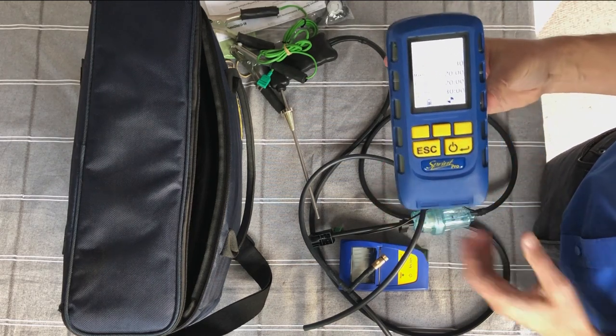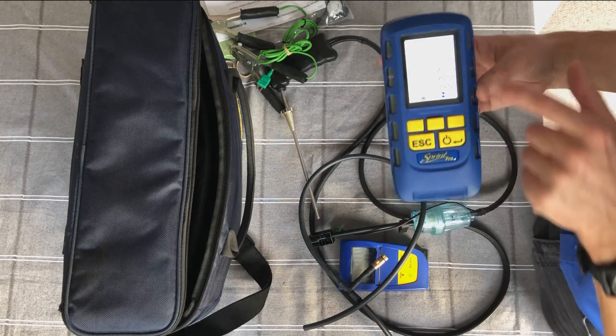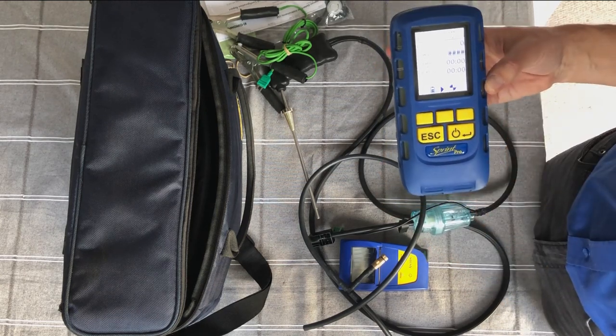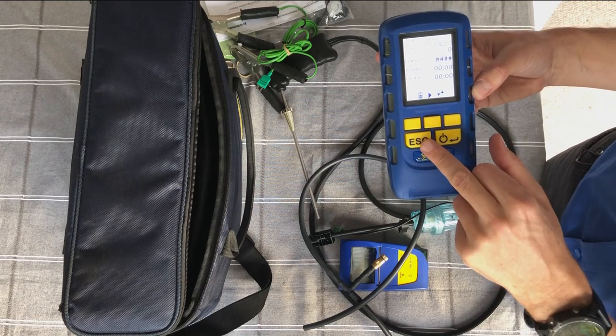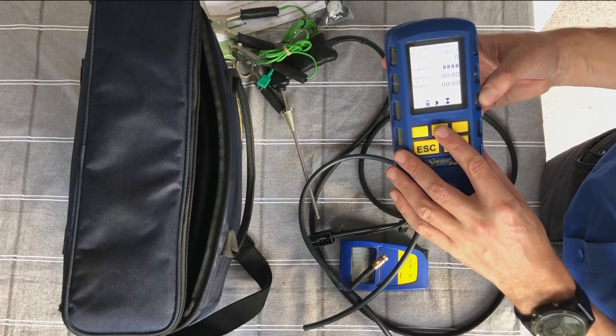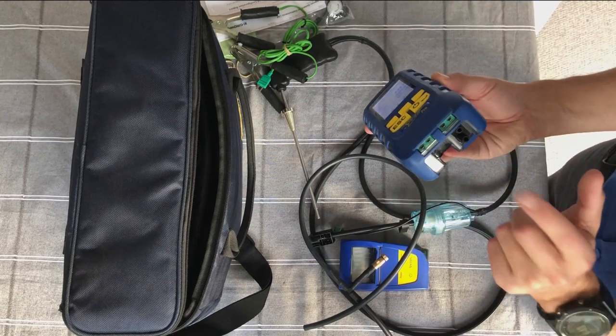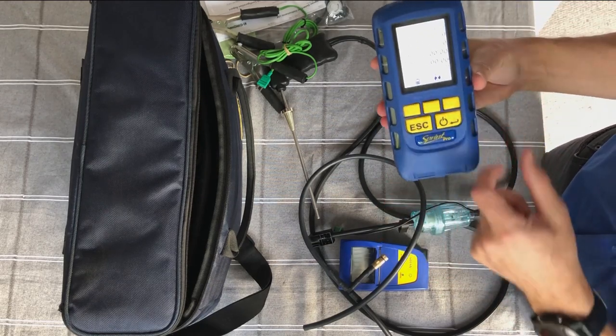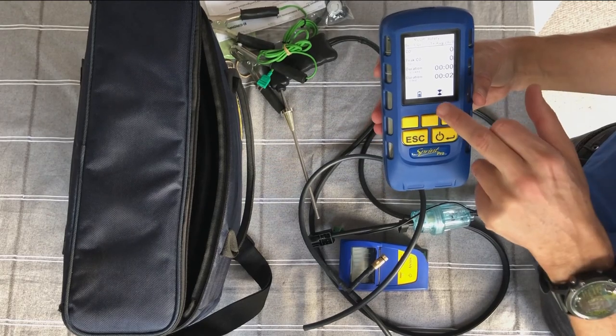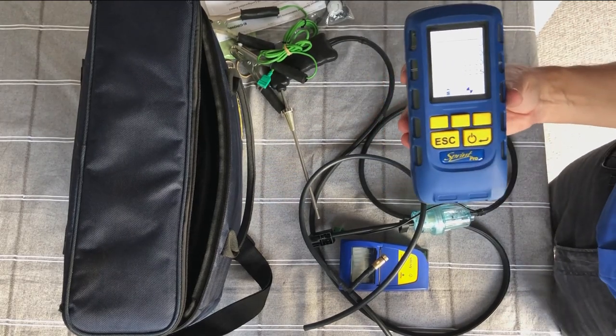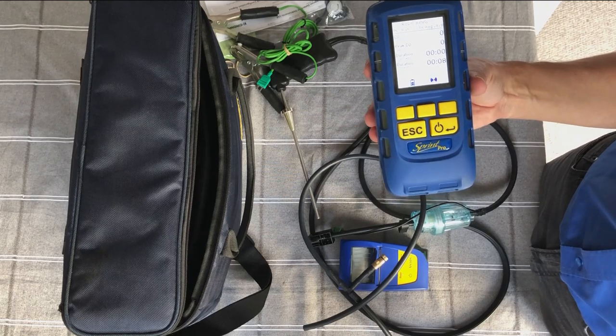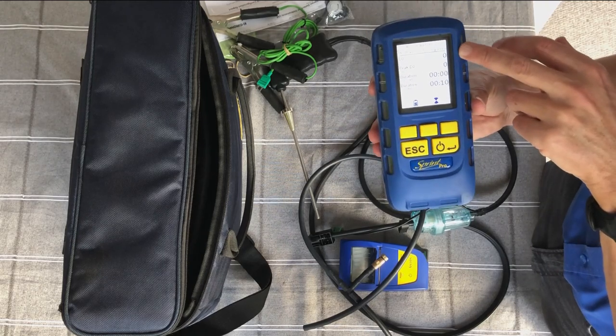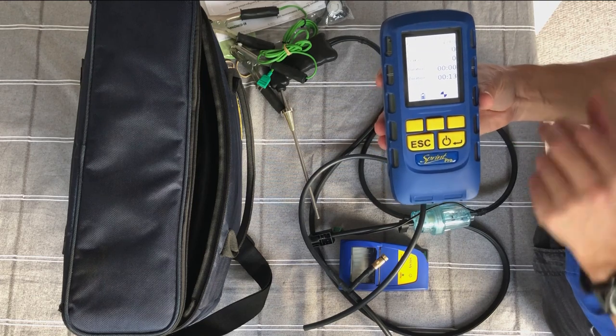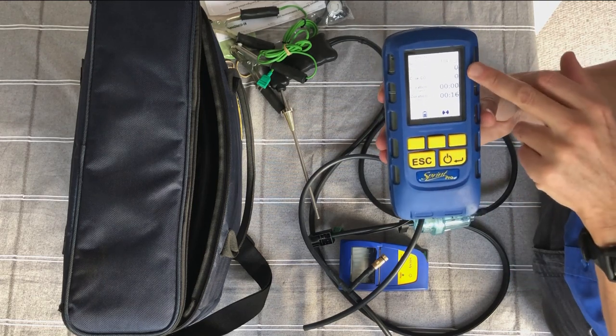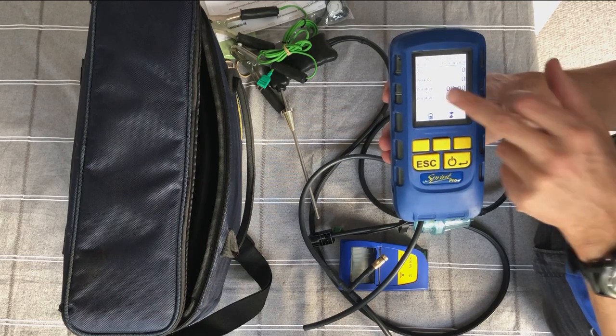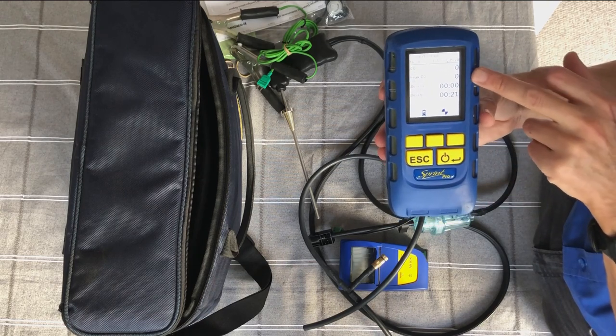You don't have to go away and find your British standard and remember what they all are. On one of the pages here, it tells you what the pass and fail parameters are. But when you're ready to start, you've got it all set up on your tripod. Again, you stick your flue probe in, connect it all in. When you're ready to go, press start, and you've got your timer there. The stop button won't come up until the minimum duration has been shown. So obviously, hopefully in here I've got no parts per million of CO, which I haven't, which is good. But if you've got some CO, it would read on here, it would show you the maximum you've seen, the peak CO, and it will show you the duration of the test. So that's the current CO, the peak it's seen, and the duration.